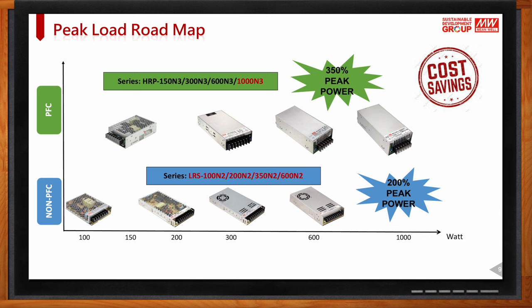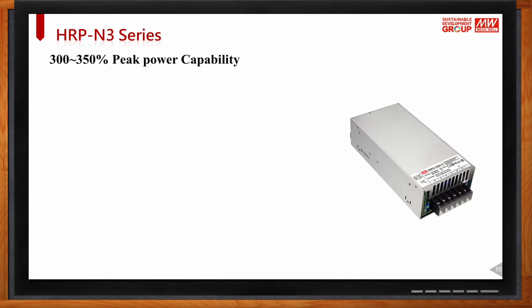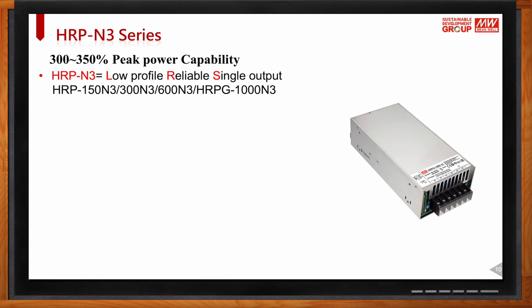So the HRP can be overloaded 3.5 times its rated output power for five seconds. For the LRS series, we offer N2 which is 200% — for example, a 100W power supply can be overloaded to 200W for five seconds in the same form factor. The HRP comes with PFC (power factor correction) from 150W up to 1000W. The LRS comes without PFC, making it more economical. For customers needing power factor correction, the HRP is available in 150W, 300W, 600W, and 1000W.